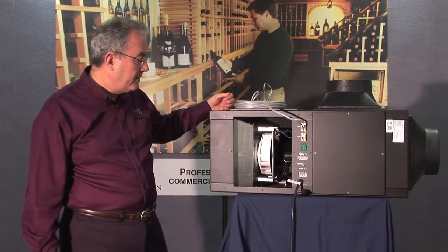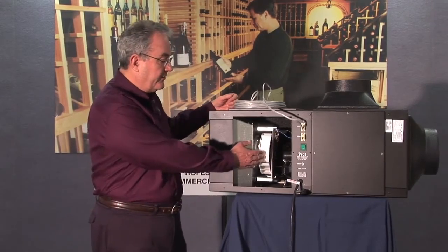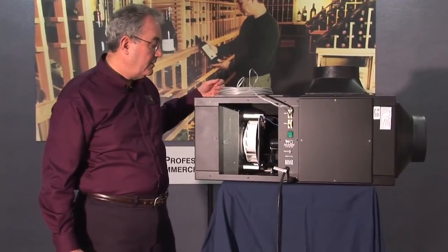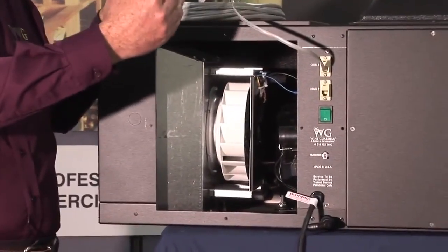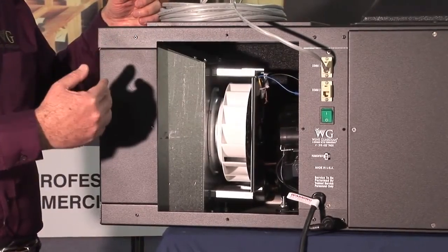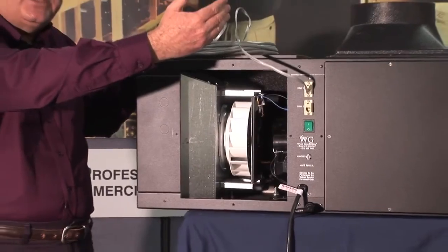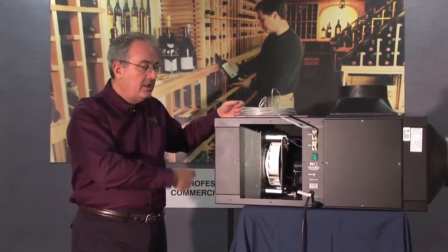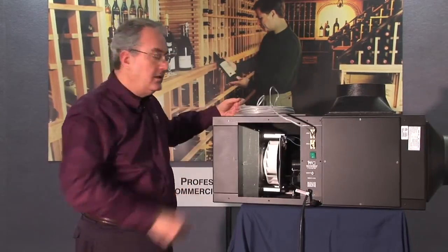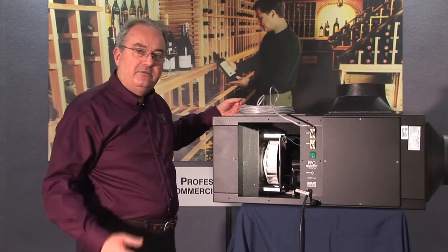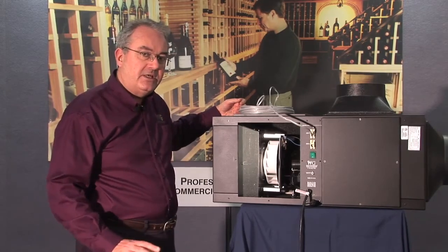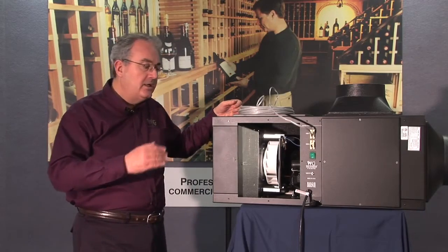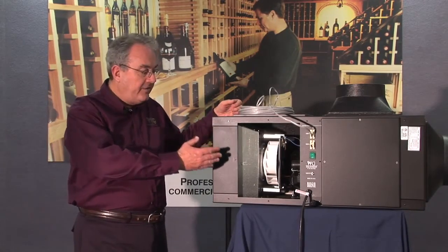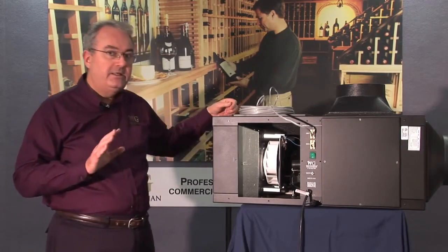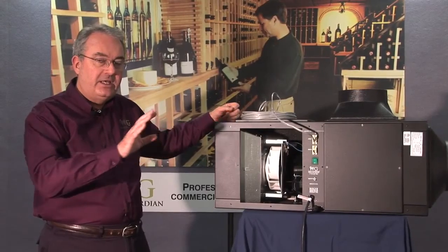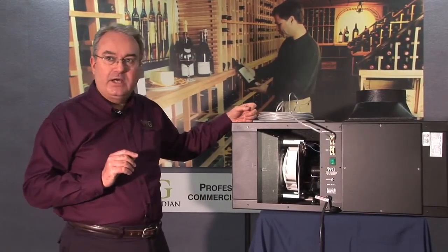If we look inside, we can quickly see the commercial grade features, notably this centrifugal fan or impeller, motorized impeller, which is used in all of the products. By the way, this unit really consists of two separate airflow patterns. There's no air exchange between the cellar and the outside environment. So essentially you have one airflow on the cellar side and one airflow on the outside of the cellar. And that's a good reason to use a ducted system, because these units are generally installed outside of the cellar. You can run ducting on both the condenser side and the evaporator side. So if you ever did need to get into the unit to work on it like this, it's done in most cases in an adjacent room.